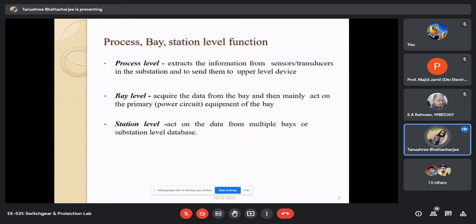So I have told you about the process level, which takes information from the transducers or sensors and sends it to the upper level, which is bay level. Bay level has the data from process level, and it actually takes it inside the IEDs, and IEDs do their operation, just like how a relay operates, they will operate and take decisions, and also log the events in their data logging system. Then comes station level, where we monitor whatever operations have happened in a substation.